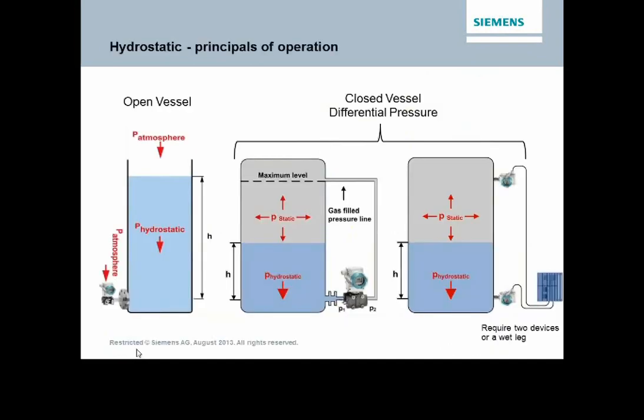When we look at measurements in vessels, we find that every measurement that we make is actually a differential measurement. So if it's an open vessel, we refer to that as gauge pressure measurement. We're still measuring differential. We just happen to be sharing the same point at the top in terms of an opening in the tank. It's a little more complicated when we're doing closed vessel applications. And some of the challenges there are what helped to develop radar. So, some of the challenges would be if I have a process tank that's pressurized and I want to get a proper measurement from a differential pressure device, I have to be able to bring what that pressure is to the device so that I can offset that measurement. Otherwise, I would simply see that pressure in the tank as additional product.